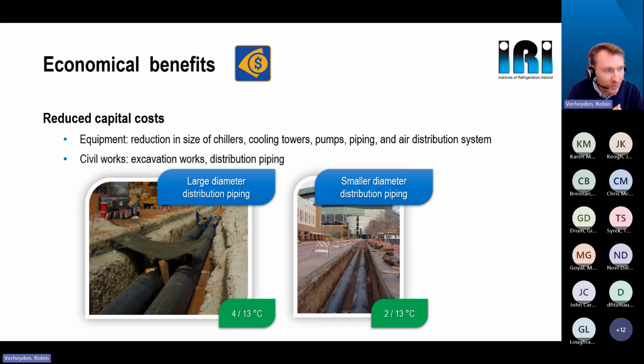In addition, with district cooling plants, the delta T is bigger. That means the piping can be smaller because the flows through the piping will be smaller as well. This is an additional cost saving on top of smaller pumps, piping, and air distribution systems.